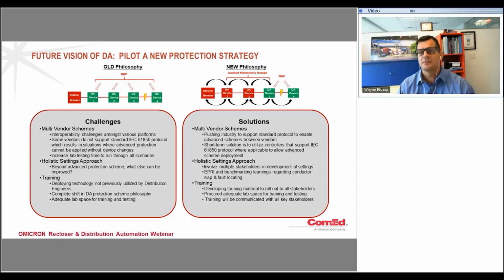Some things to note about our new philosophy on the right here. Each device will only communicate to its neighboring devices. If a device senses overcurrent, it will send out a signal to its neighbors. And each device needs to see 2 signals to shift to its slow tripping.